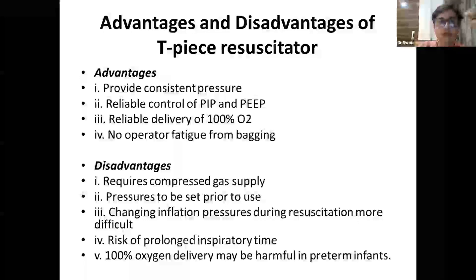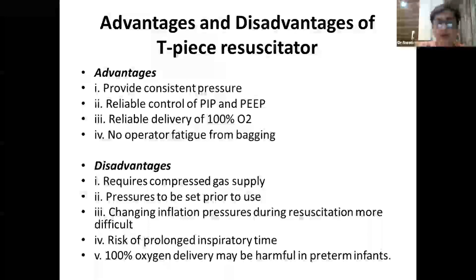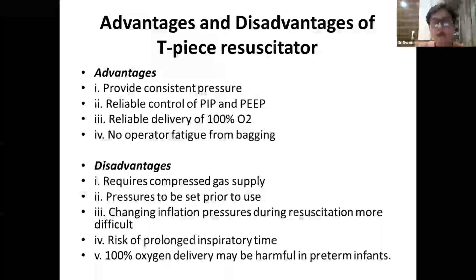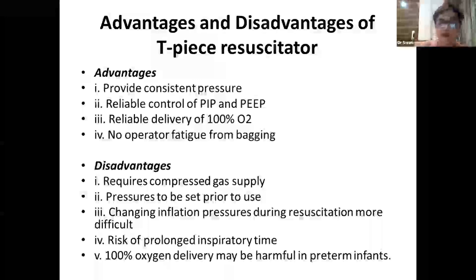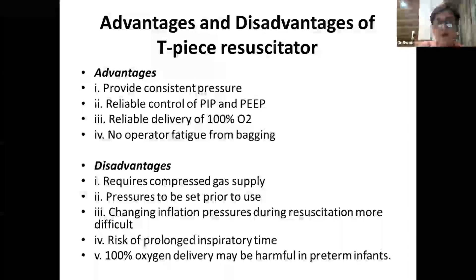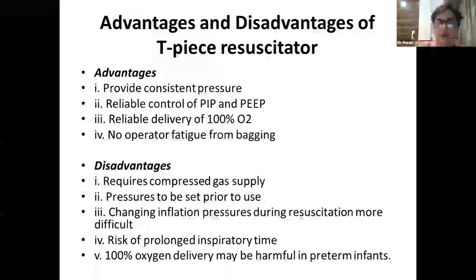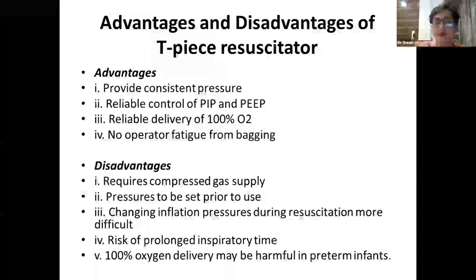There is no operator fatigue from bagging; however, it requires a compressed gas supply, which can be difficult during transport without a cylinder. Pressures need to be set prior to use and cannot be easily changed during resuscitation. There is a risk of prolonged inspiratory time if the PEEP valve is occluded too long, and 100% oxygen may be harmful in preterm infants — blended oxygen and pre-ductal SpO2 targets should guide FiO2 setting.